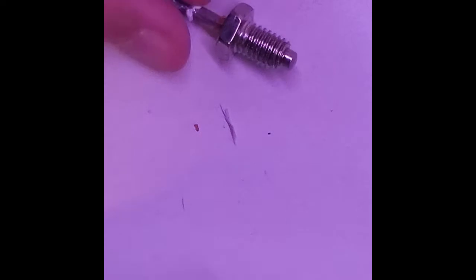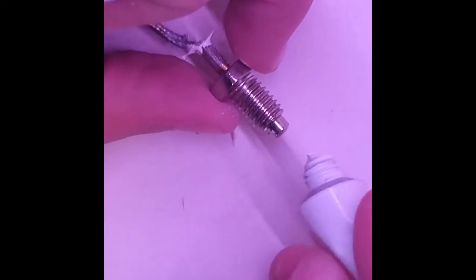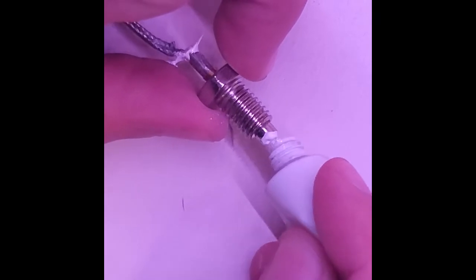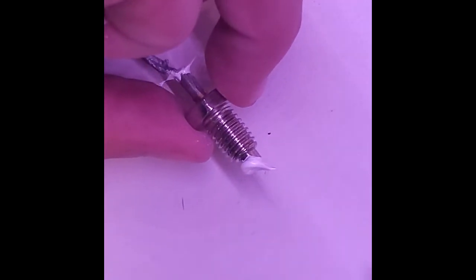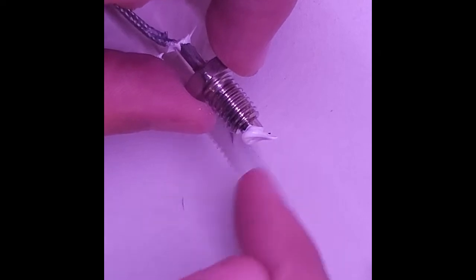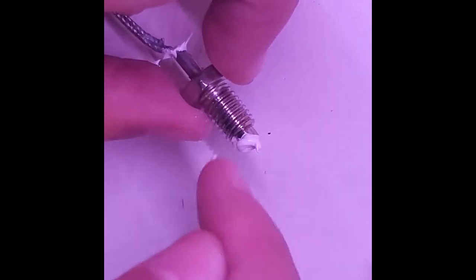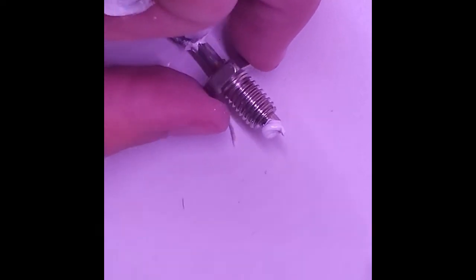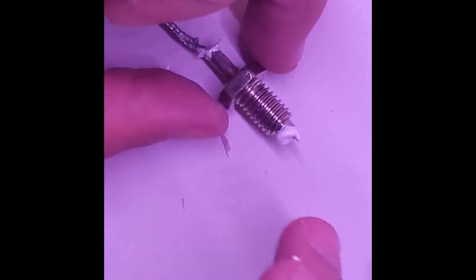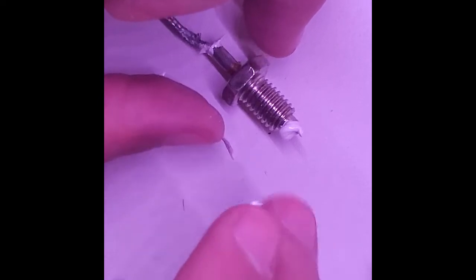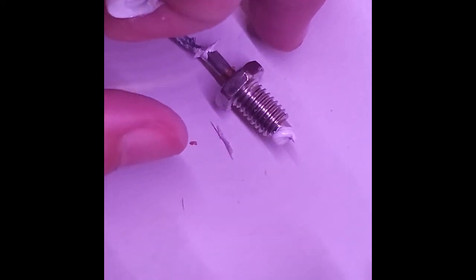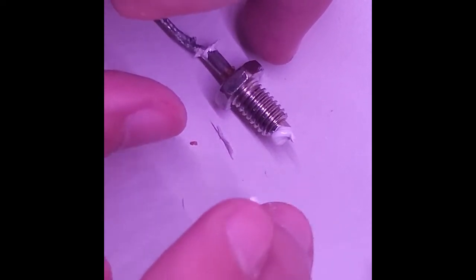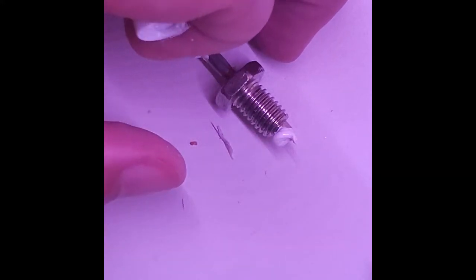Also, when you go to screw this into your threaded hole, make sure to put some thermal paste on the outside here so you get good heat transfer from the surface that you're screwing into to the casing, because you can also have an air gap there. This is really critical if you're screwing this into, say, a hot plate if you want to get an accurate temperature reading. I've never seen anyone talk about this, so you must do this if you want an accurate reading.